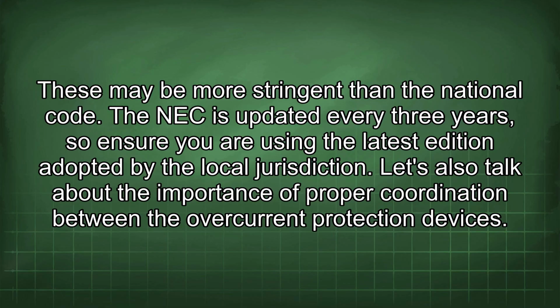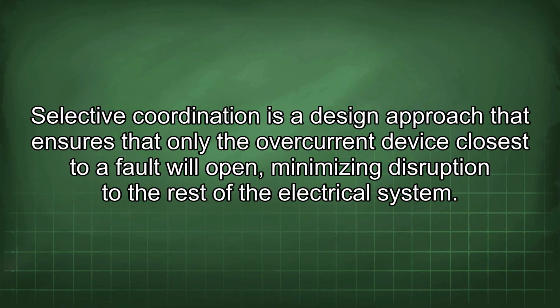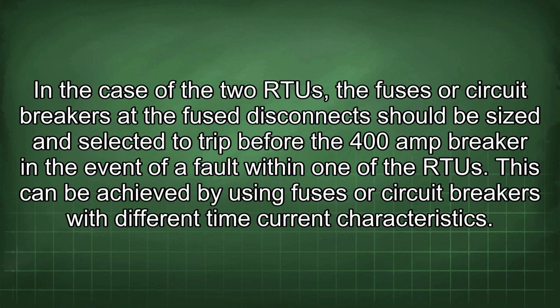Let's also talk about the importance of proper coordination between the overcurrent protection devices. Selective coordination is a design approach that ensures that only the overcurrent device closest to a fault will open, minimizing disruption to the rest of the electrical system. In the case of the 2 RTUs, the fuses or circuit breakers at the fuse disconnect should be sized and selected to trip before the 400 amp breaker in the event of a fault within one of the RTUs.